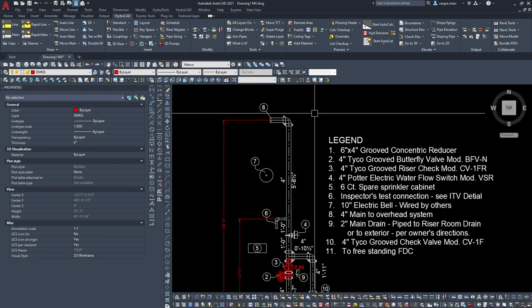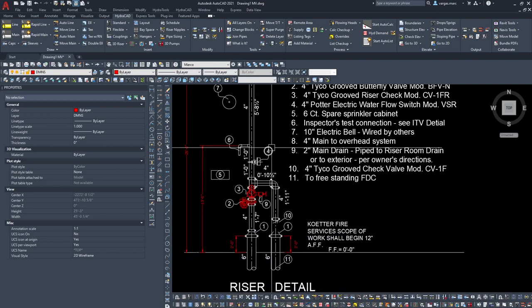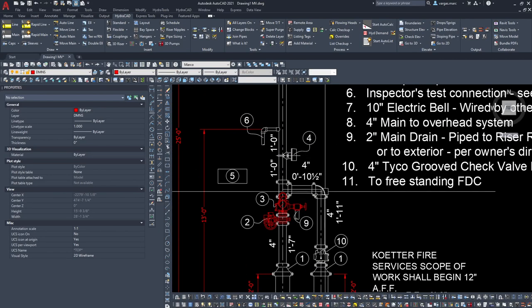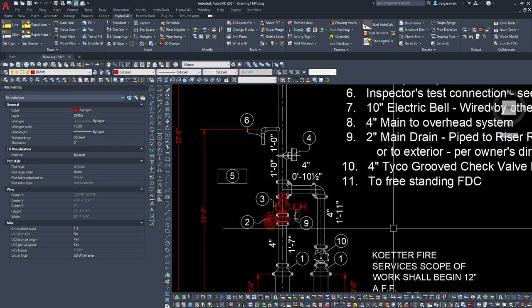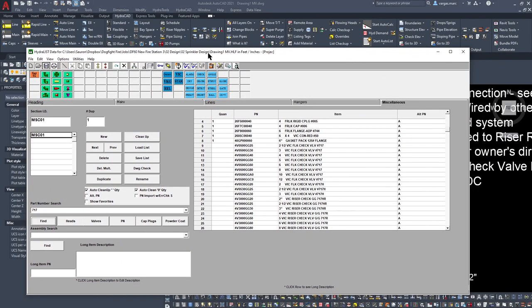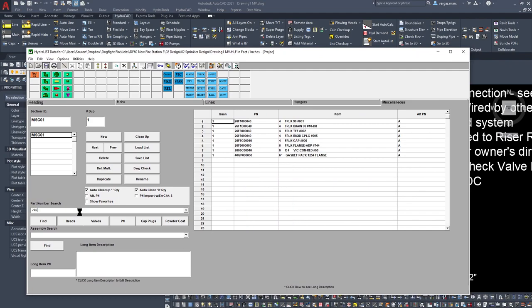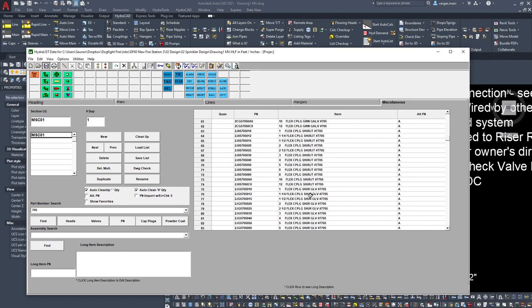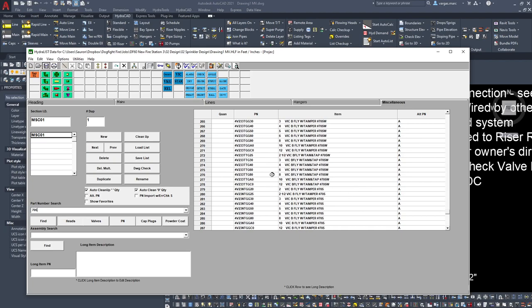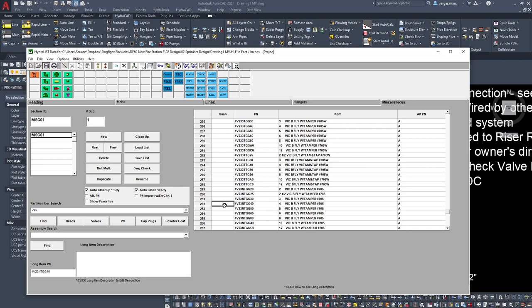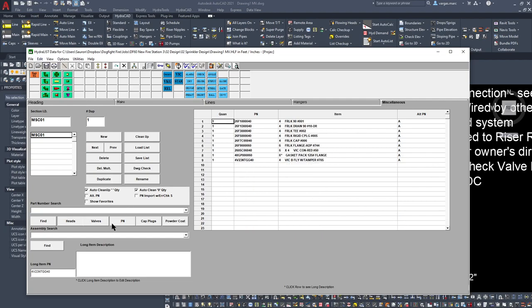So we don't need the check valve, but we do need our butterfly valve. The part for the butterfly valve is the Victaulic 705. I'll search for 705 and scroll through the list until you get to your Vic butterfly. Don't choose the 705W — that's a discontinued model. We're going with just the regular 705. There's our butterfly valve. I know that our riser check is a 717R.